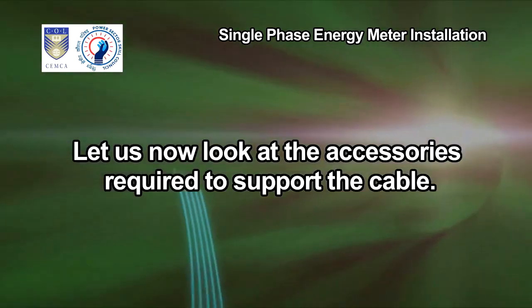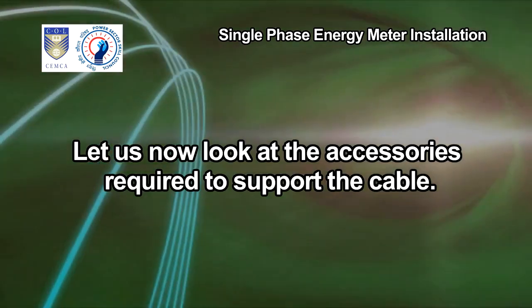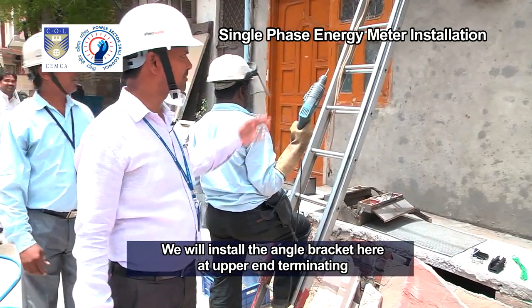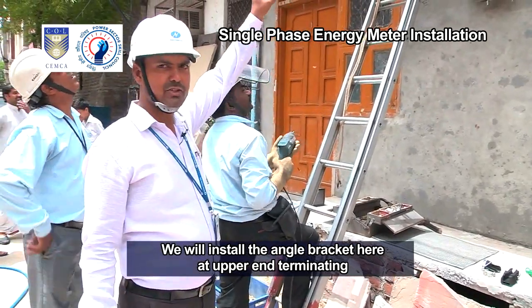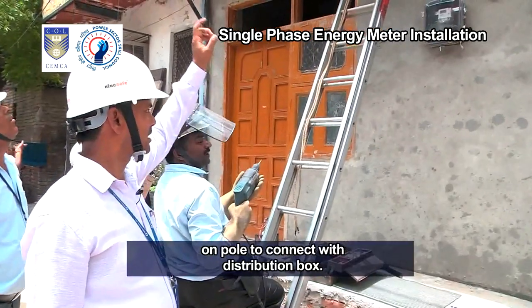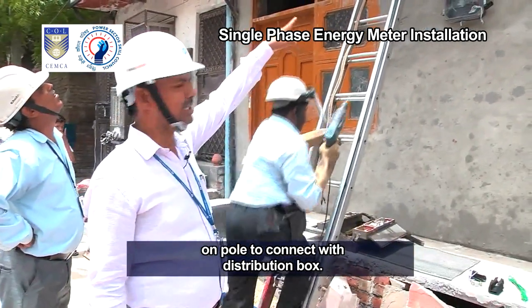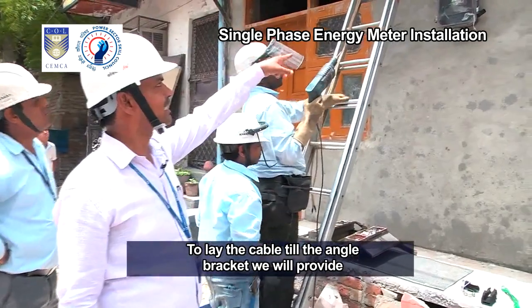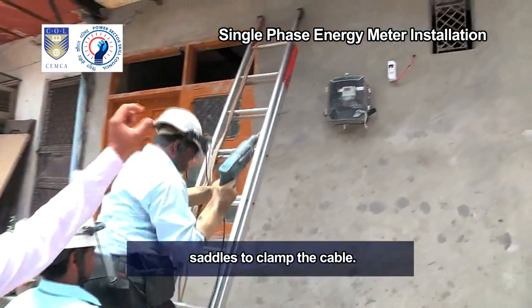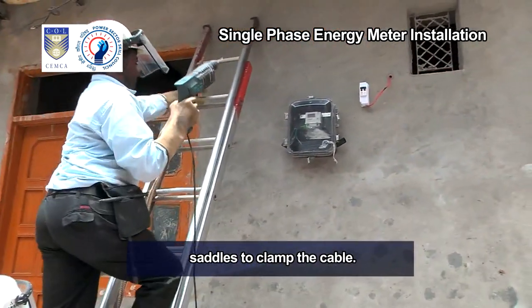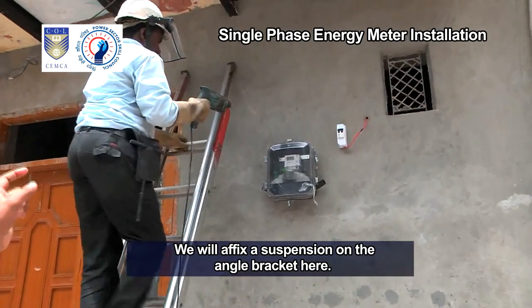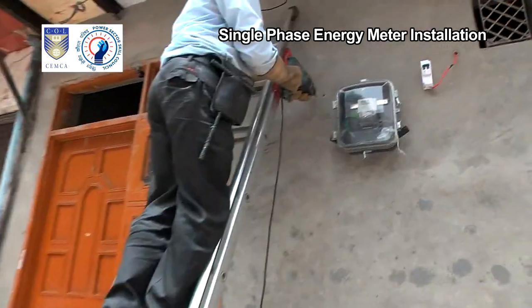Let us now look at the accessories required to support the cable. We will install the angle bracket here at the upper end, terminating on the pole to connect with the distribution box. To lay the cable till the angle bracket, we will provide saddles to clamp the cable. We will affix a suspension on the angle bracket here.